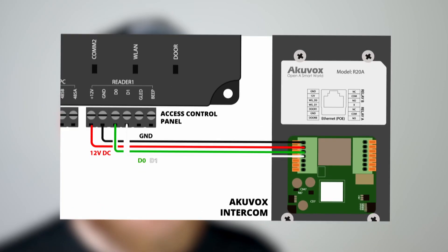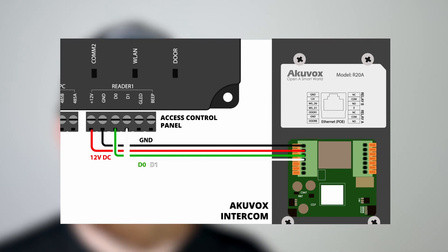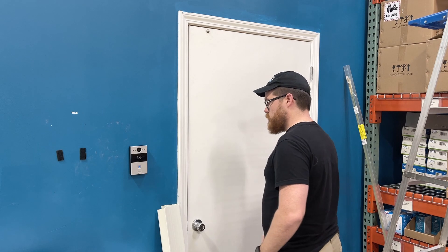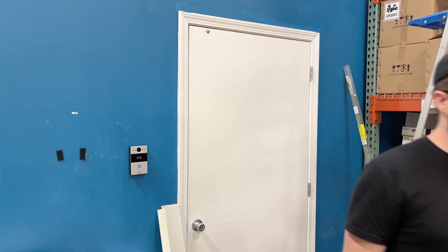Your Akuvox intercom now functions as a generic card reader for your access control system. Let's go test this out. For this example, I have a proximity card that is not registered with my access control panel. You can see I scan it — as you would expect, nothing happens. The door doesn't open, no access has been granted. Now in the second example, this card has been registered in the access control system and assigned a user. As you can see, the door opens and I can walk right in.